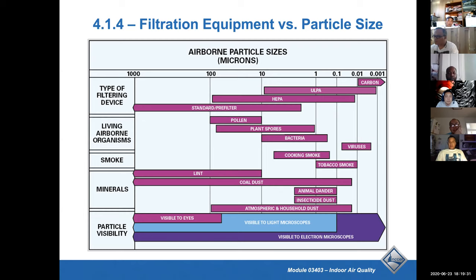A MERV 8 filter can cost anywhere between $5 and $10, and a MERV 13 costs $40, $50. It's anywhere between four to eight times the cost of a regular filter. So say it costs us $5,000 every 6 months to change filters in our building. When we go to the higher MERV filters, it's going to cost us five times more, about $25,000, so about $50,000 a year just to increase our filter efficiency.